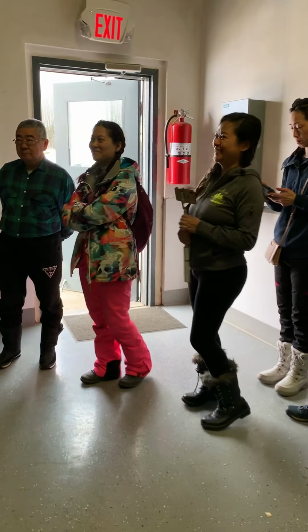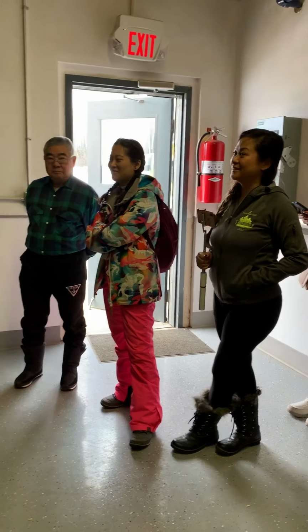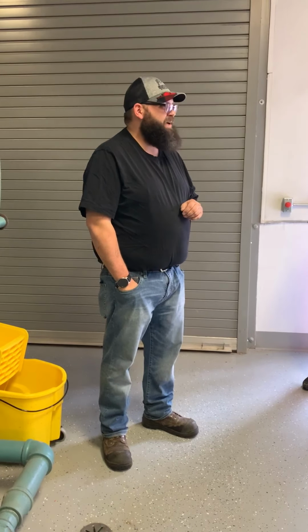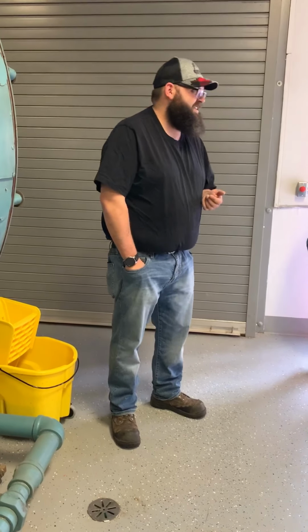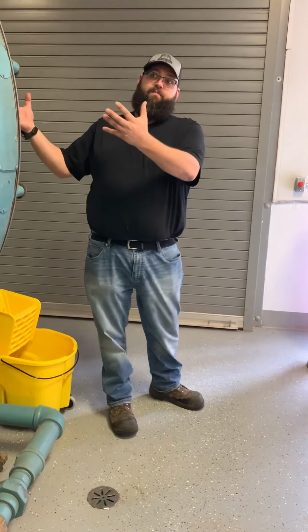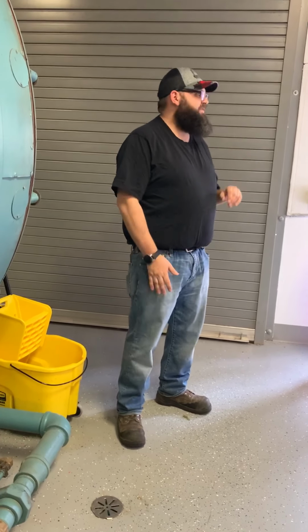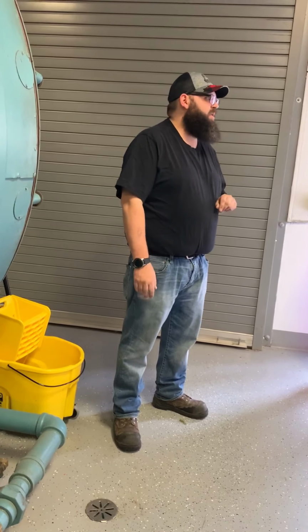It was still going on a little bit when the first group got here, but by the second group we had it all closed up and buttoned up. It was a stressful couple of weeks because we couldn't make oil during those weeks. But now that those fresh tubes are in there, our boiler's good for a minimum of 5 years before we even have to start worrying about it again.